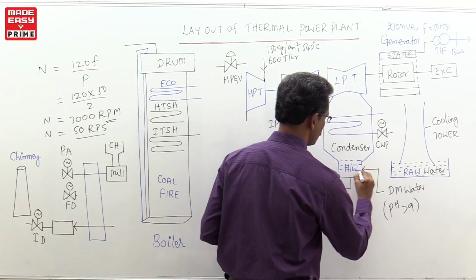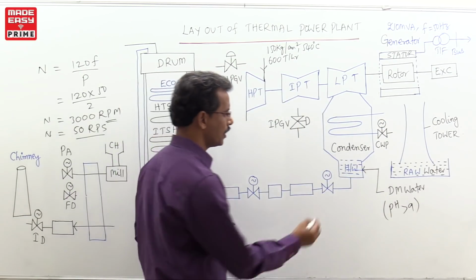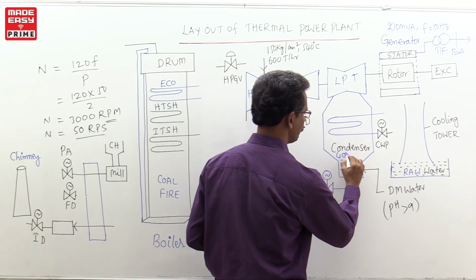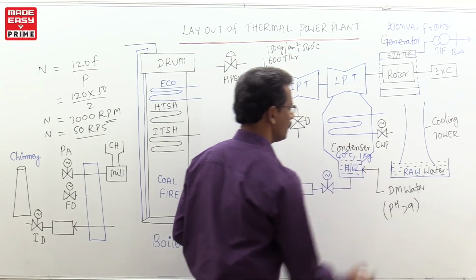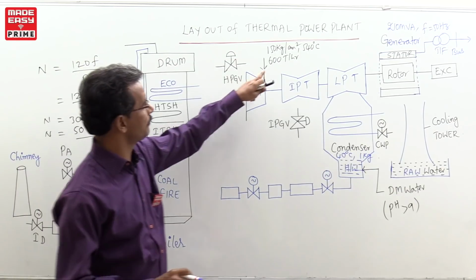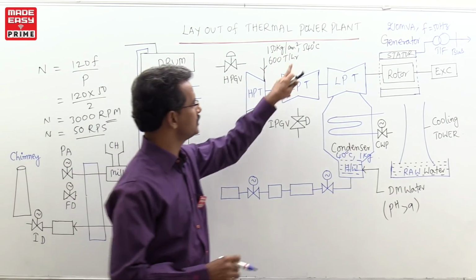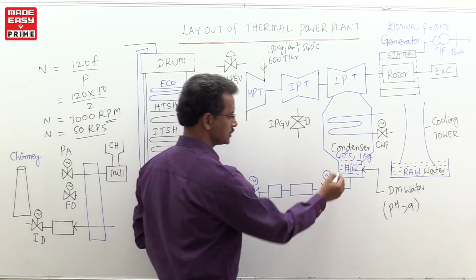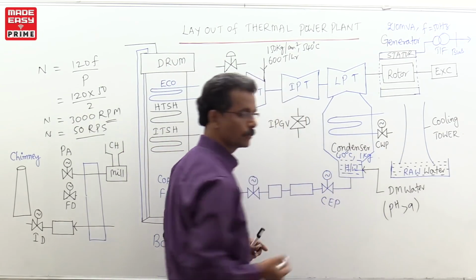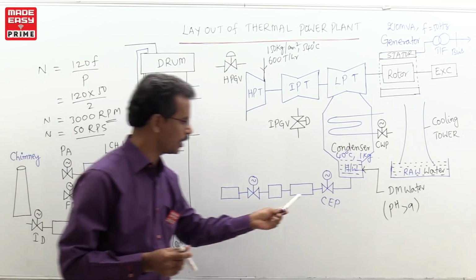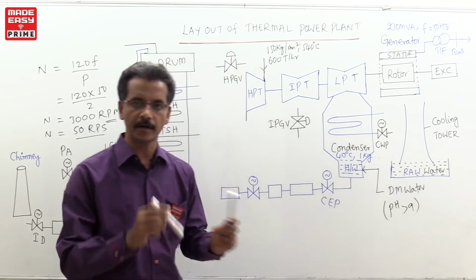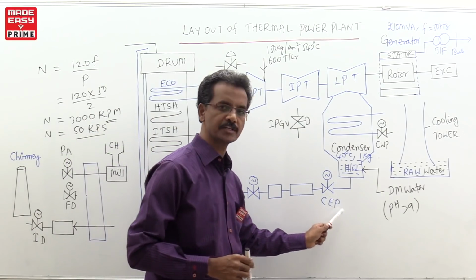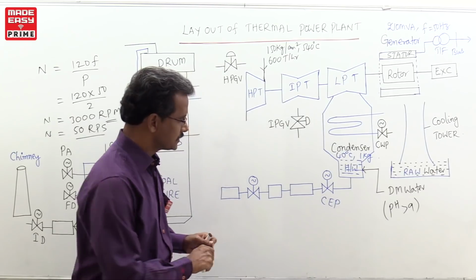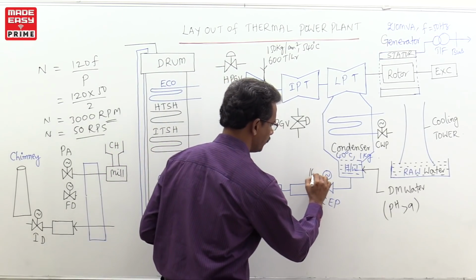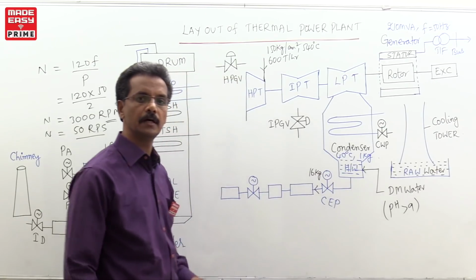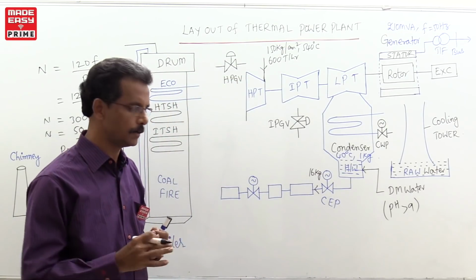This is the hot well at a temperature of 40 degrees centigrade, think of 40 degrees centigrade, and at atmospheric pressure of 1 kg. But what is our requirement? For producing these requirements, this water passes through a pump. This is called the condensate extraction pump. I am not writing the names, but I am explaining. The output of this condensate extraction pump produces a pressure of 16 kgs per centimeter square.